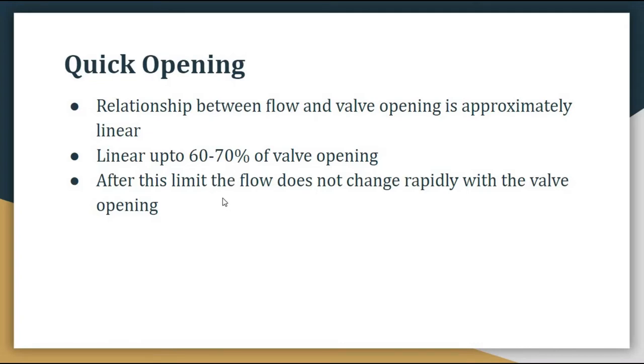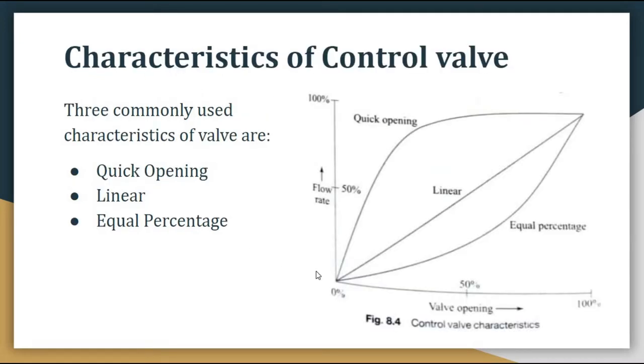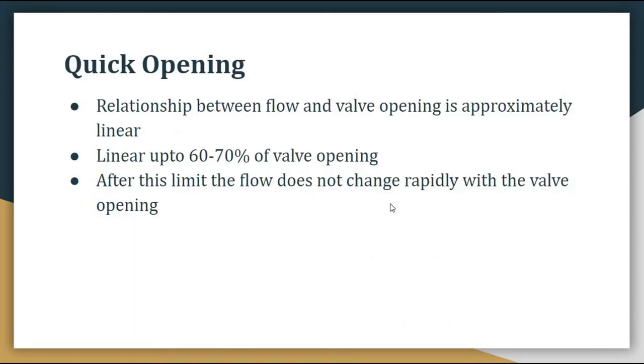After this limit, the flow does not change rapidly with the valve opening. On the x-axis we have valve opening, and on the y-axis we have flow rate. As we move along the x-axis, we are opening the valve more, and as we move along the y-axis, the flow rate of the fluid increases. In quick opening, up to 50 to 60 percent of valve opening, the characteristic is almost linear. After that, valve opening keeps increasing but flow cannot follow it as rapidly.